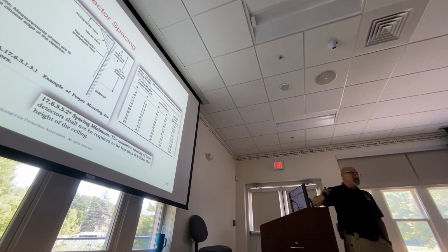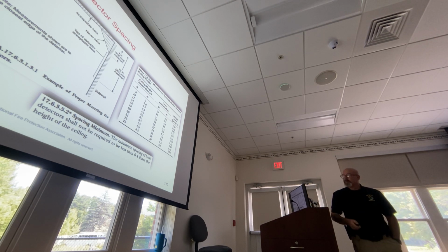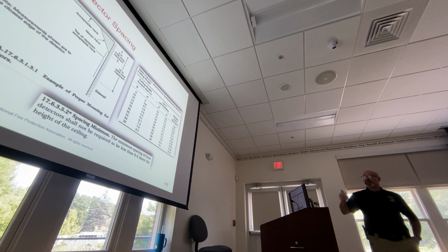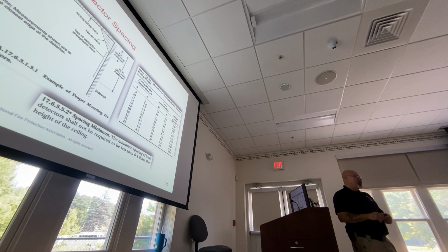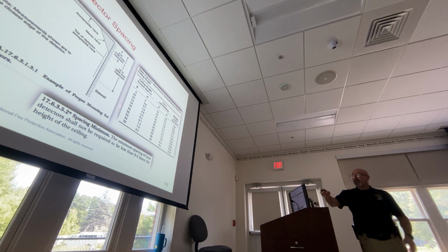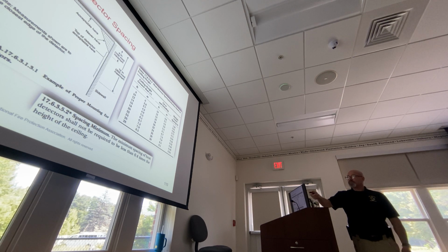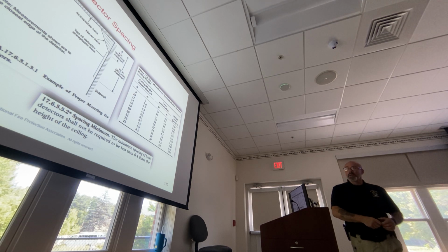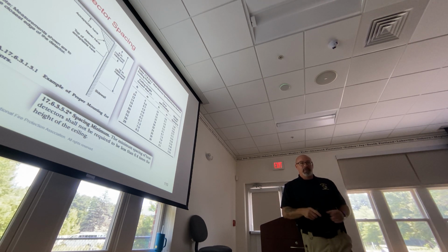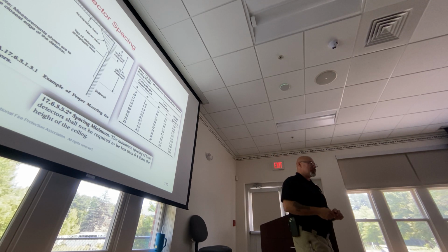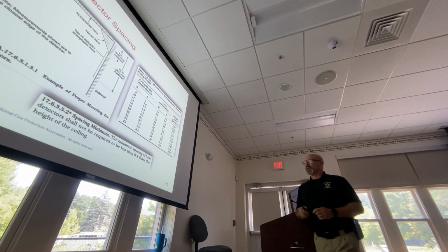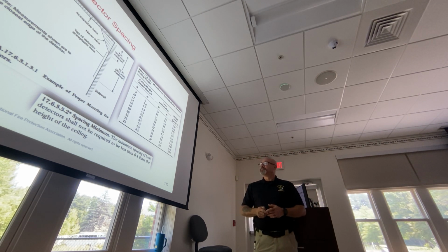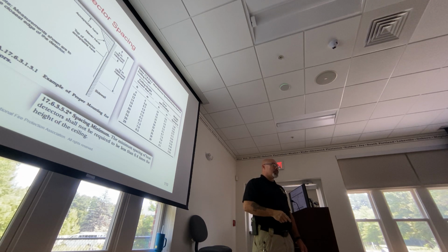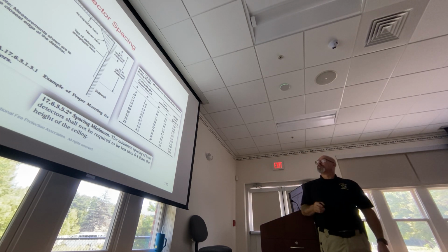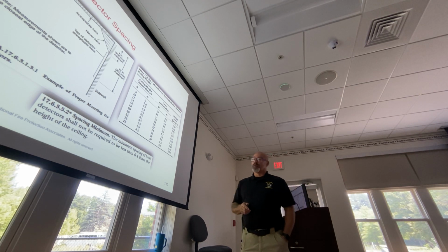We're not getting into design criteria here. So, as an example again, if I have a 25-foot ceiling height, what's my multiplier? 0.46. Okay, because it falls within 24 to 26. 0.46 is my multiplier. We can get into a lot more specifics in another weeks-long class if we wanted to go that route. That's not where we're going here. Actually, it's more than a week long for design. Okay, everybody understand that? We're good with that table? Make sure you're putting a tab or highlighting table 17.6.3.5.1.